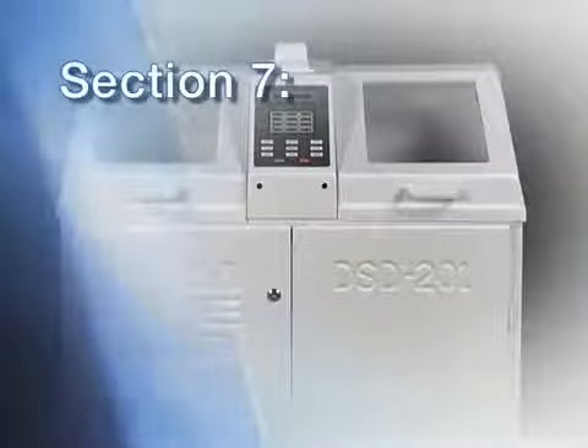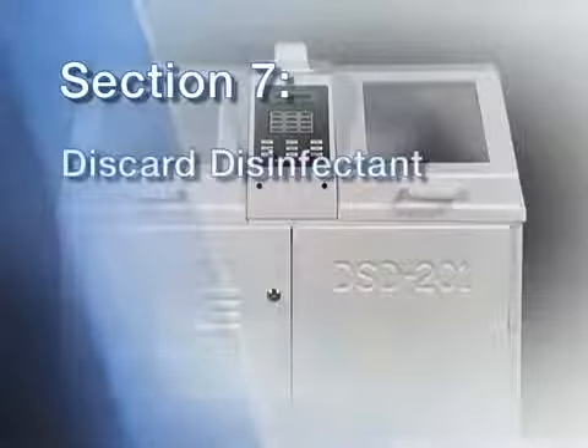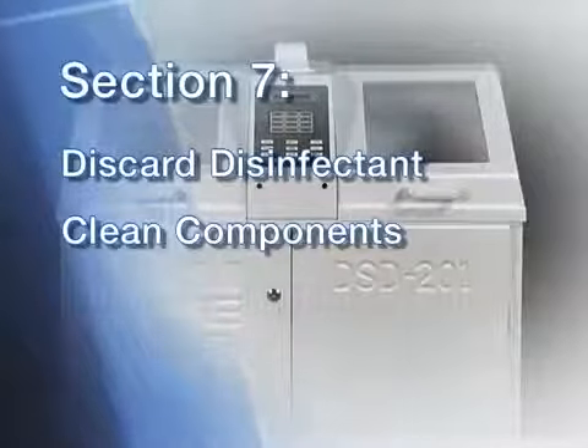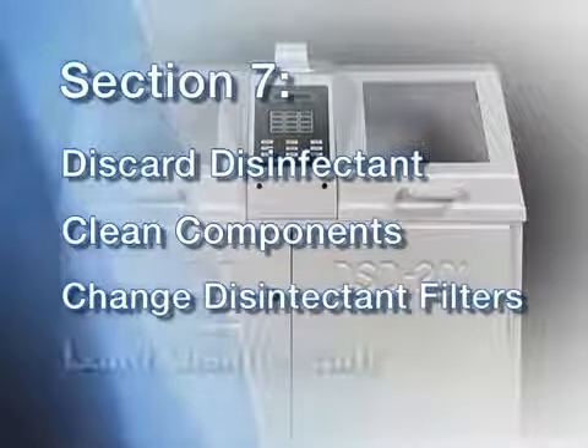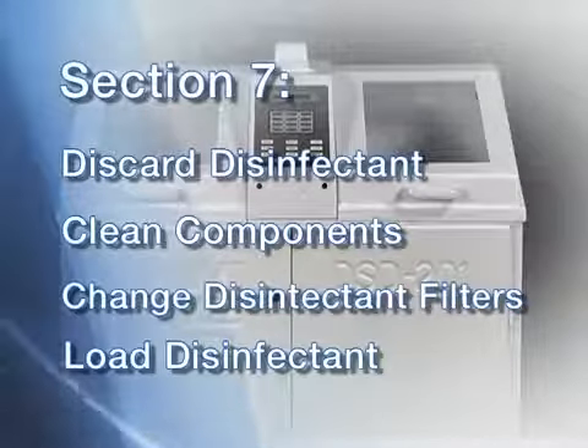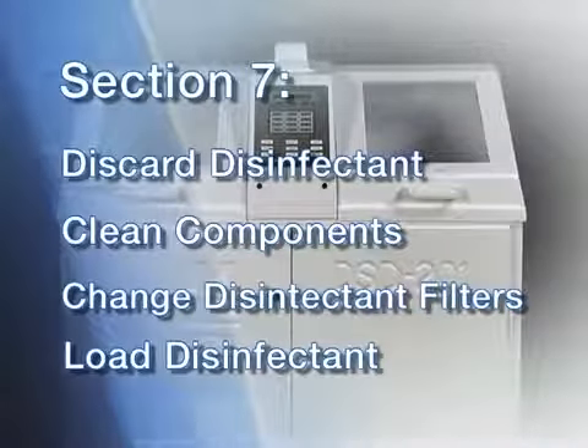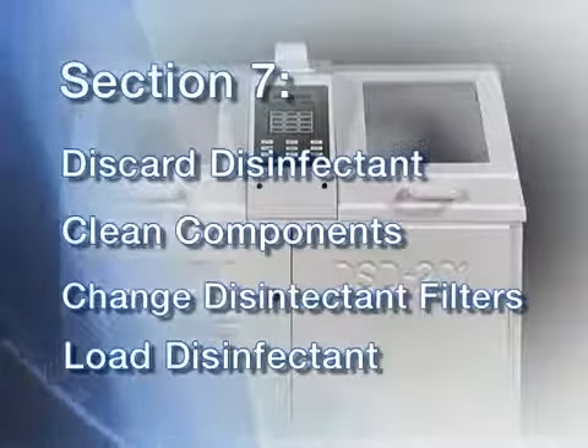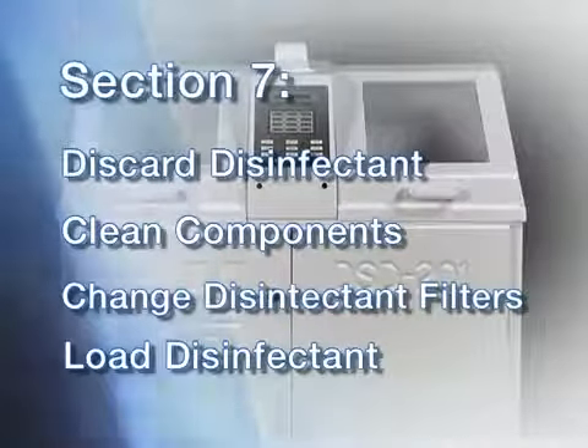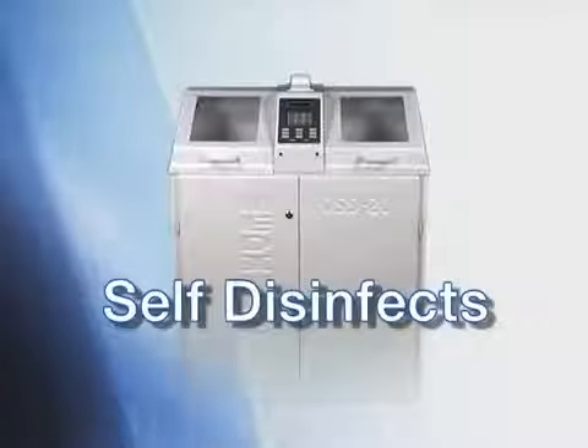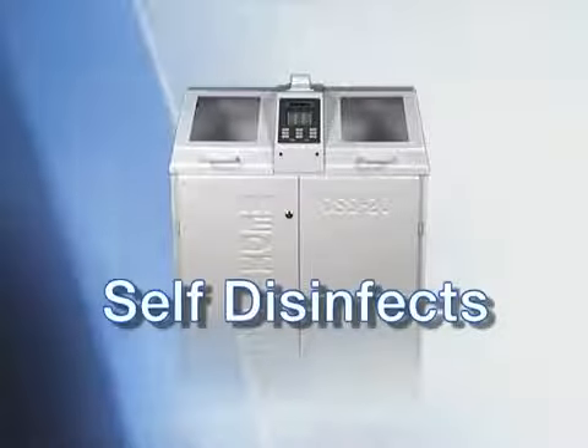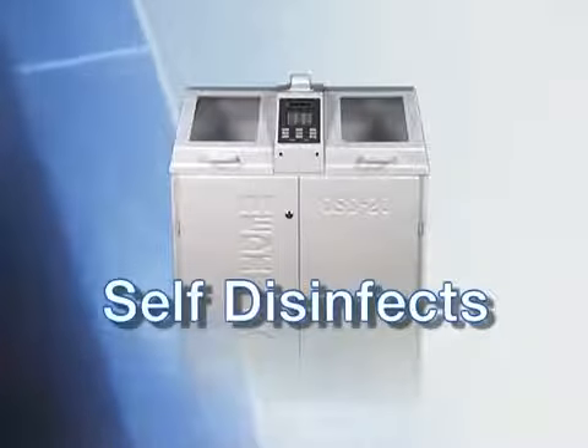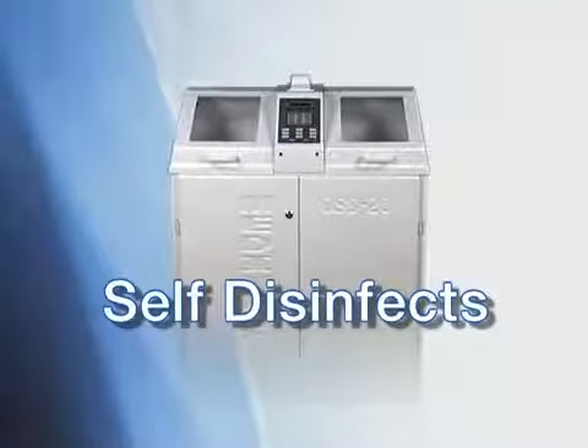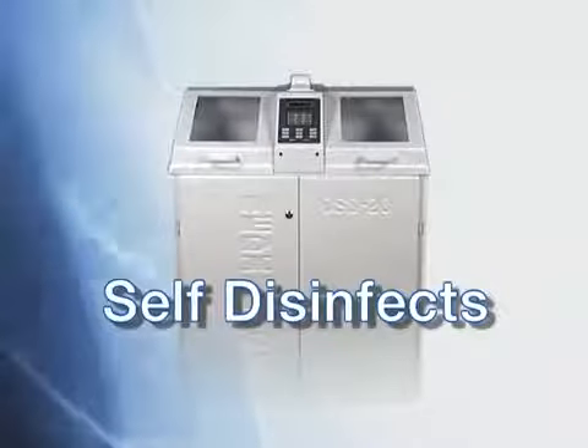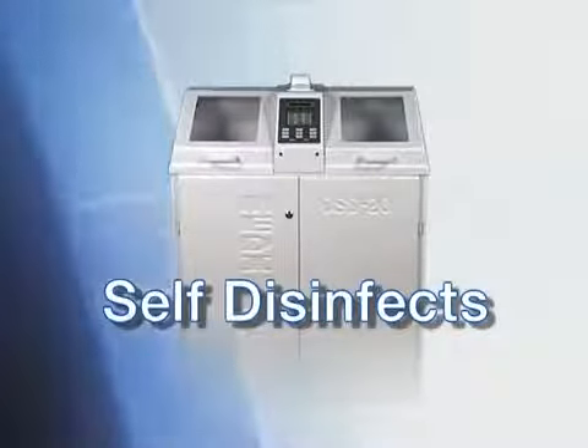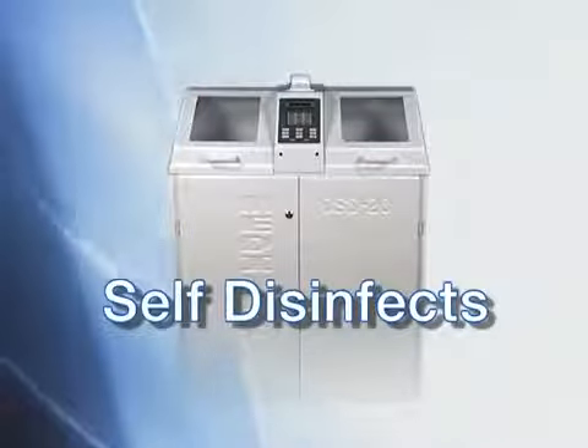In Section 7, we will demonstrate the procedures for dumping the disinfectant, cleaning the disinfectant reservoir, changing the disinfectant filters, and loading new disinfectant into your DSD-201. Loading the disinfectant can be accomplished either with the onboard automated loading system or by pouring disinfectant directly into the basin. One of the unique features of the DSD-201 automated endoscope reprocessor is that it self-disinfects during each cycle. No additional disinfection procedure is required to maintain your reprocessor. However, periodic filter and disinfectant changes are required.